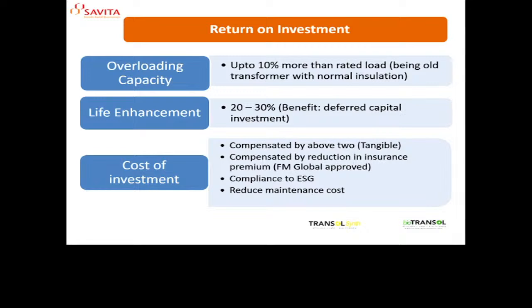So, return on investment. If you are doing all this activity, what return on investment will you get? Overloading capacity: because it is an older transformer, you can get up to 10% more than the rated load continuously from your existing transformer. Then life enhancement. We can surely say, with those experiments and all our experience, that you can get 20 to 30% more life from your existing transformer if you change from mineral to ester fluids. Then return on the cost of investment.